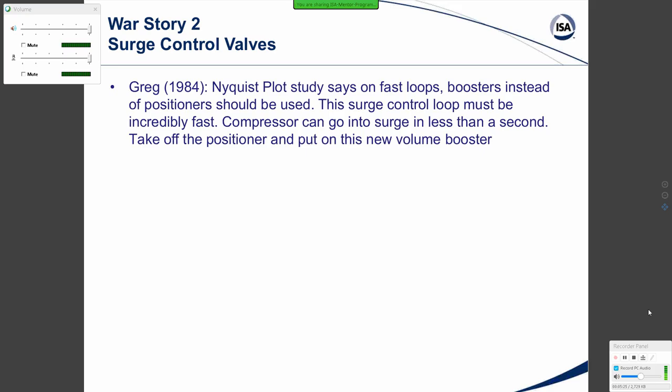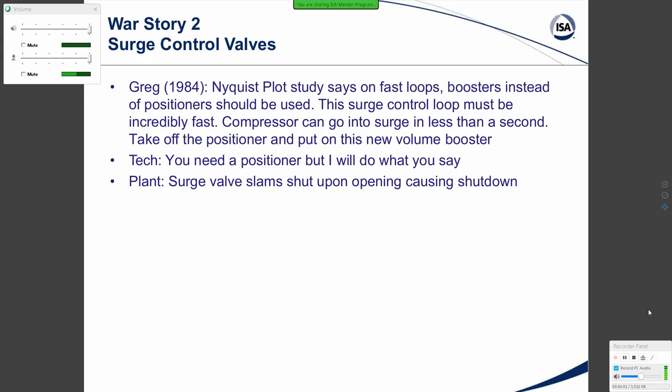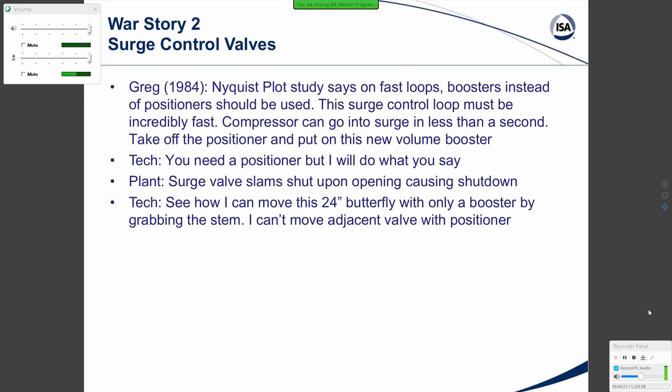War Story Two: Surge control valves. In 1984, I went into a plant for a Nyquist Plot study, and a very distinguished technologist at the supplier said valves on fast loops should have boosters instead of positioners. This surge control loop must be incredibly fast — the compressor going to surge in less than a second. Take off the positioner and put on this new volume booster. The technician said he needed a positioner but would do what I said.